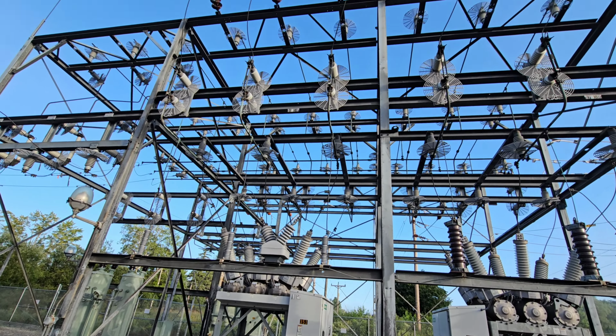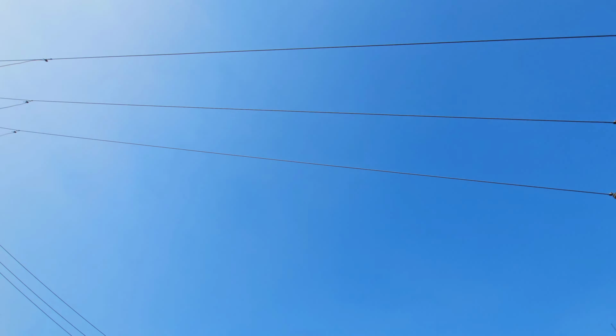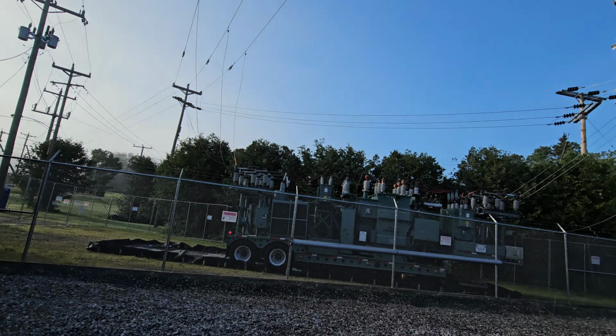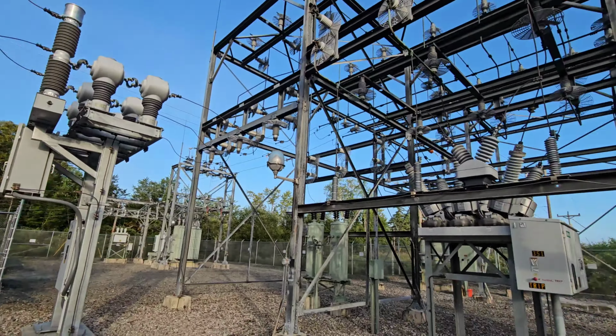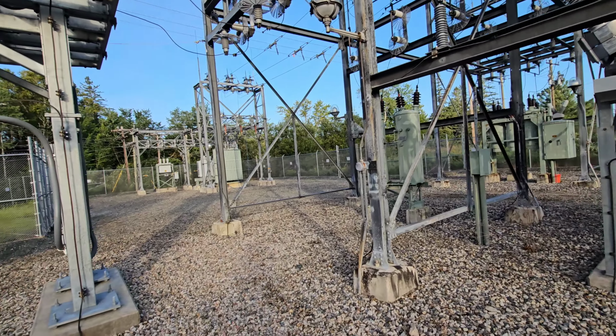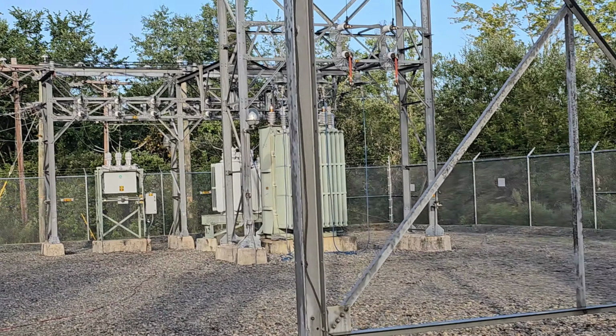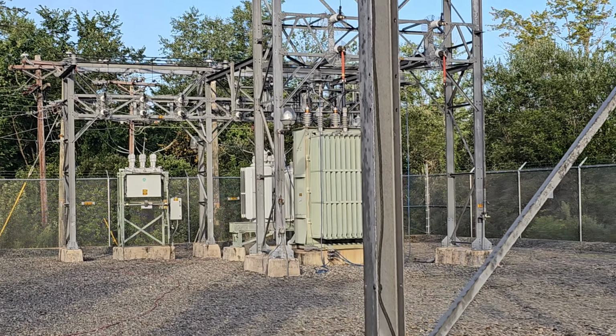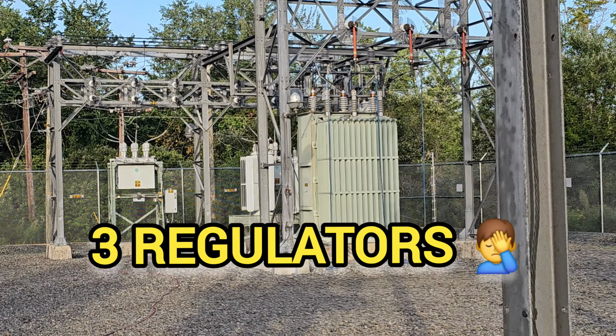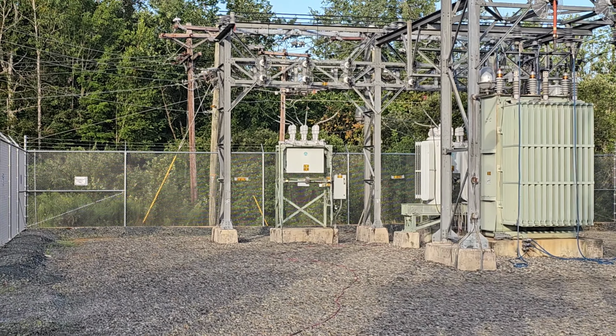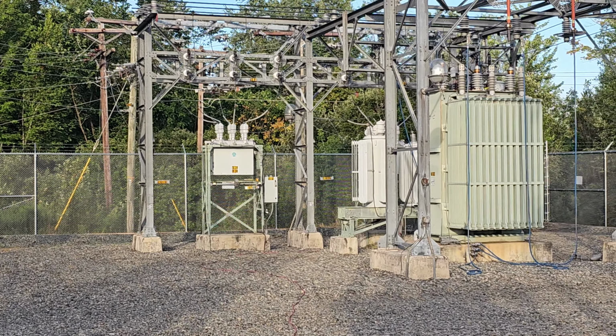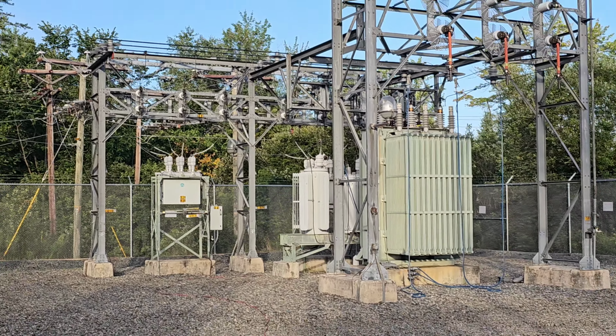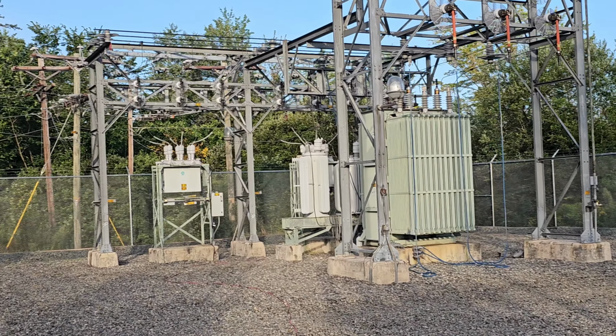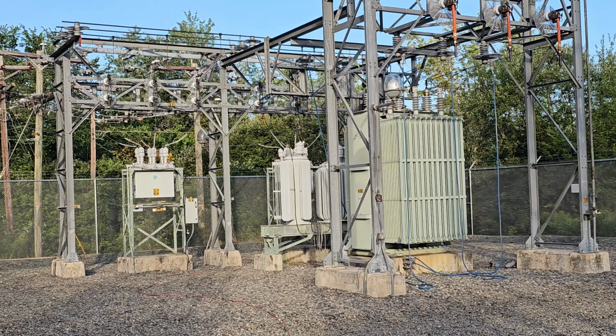So coming through on this breaker, that feeds it. Normally this power goes through that transformer, and then there's two regulators on the low side of the transformer, and then there's two breakers. So we're at a slight disadvantage while this mobile's here, because all the power that normally goes through two breakers is going through one breaker.